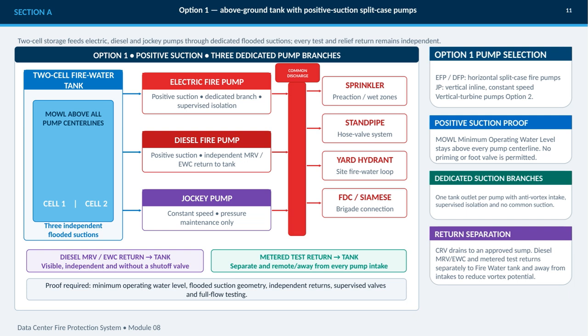All 3 pumps discharge into a common firewater header serving the sprinkler zones, standpipes, yard hydrants, and fire department connection. Return paths remain separated. The diesel minimum recirculation valve and engine water cooling return go back to the tank through a visible, independent path without a shutoff valve. Metered test water also returns separately away from pump intakes to reduce vortex potential. The design proof therefore focuses on water level, flooded suction geometry, supervised valves, independent returns, and full flow testing.